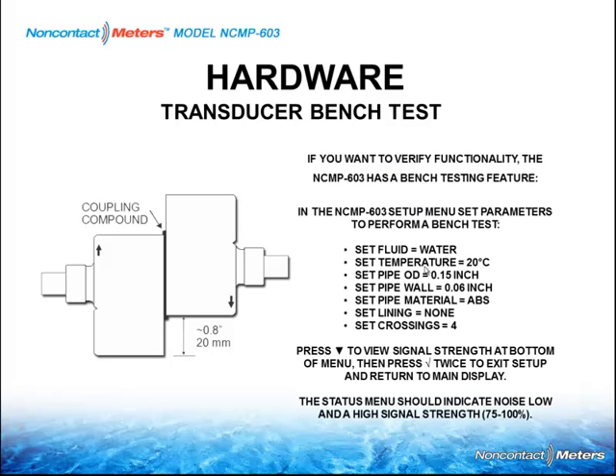Now, one really cool feature with this transit time flow meter is that you have the ability to test the functionality of the device when you're off the pipe. Sometimes we get a call from support, and they'll say, our flow meter doesn't work, and after reviewing the whole thing, it's application related. So wouldn't it be nice to know whether you had a broken cable or a bad application? If you put in an application that didn't work, you can take it off and do this test. This will validate that you don't have an equipment problem, so it just gives you that peace of mind. Through this procedure, you mount the two sensors face to face and set it up with these programming parameters, water and the spacing and so on, and the number of crossings, and it will define whether the device is functional on the bench test off the pipe.